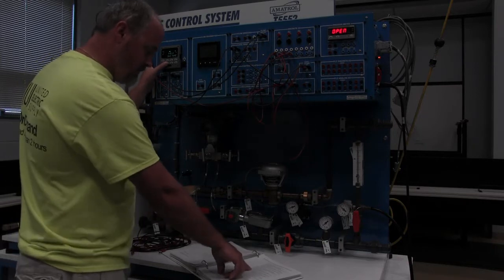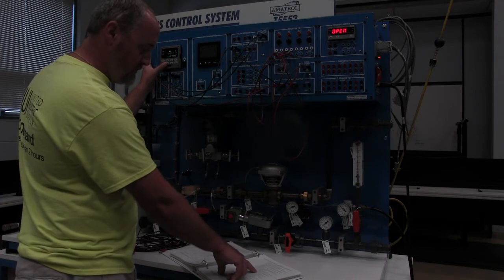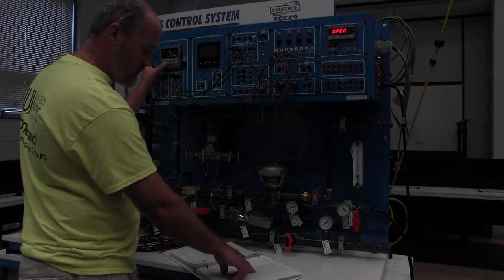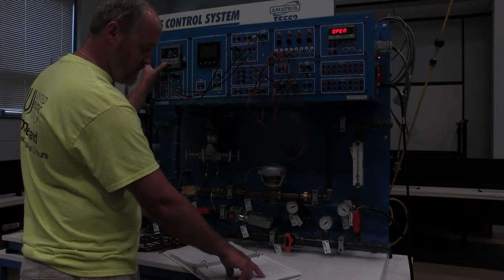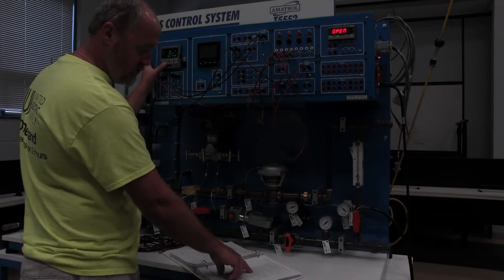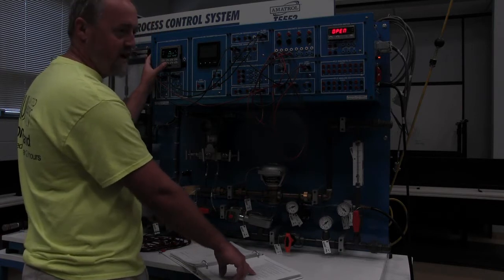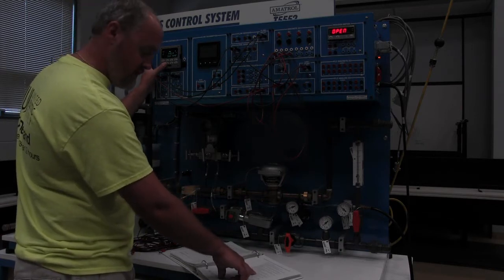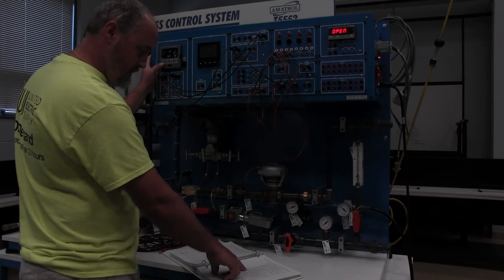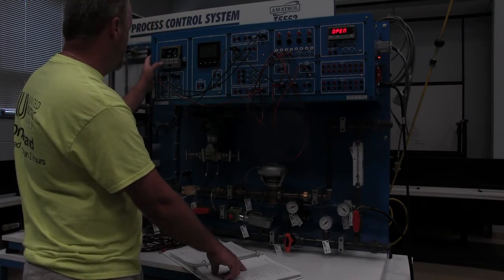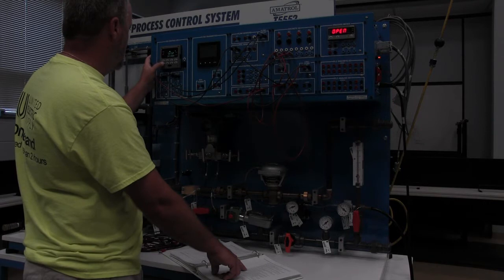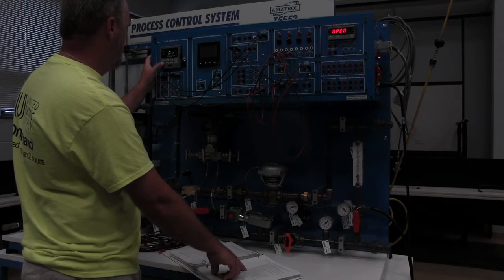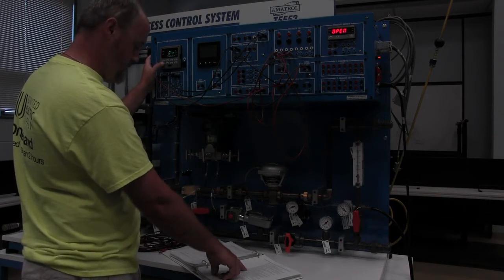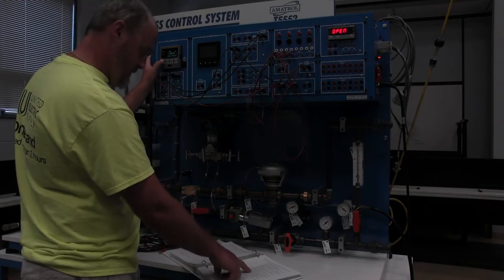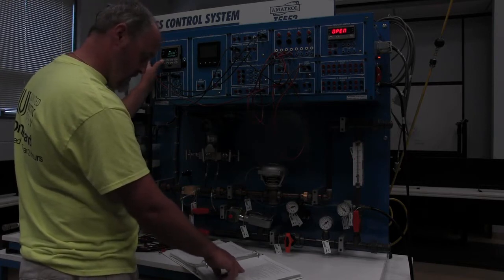The reason we're going 1 to 5 volts is the level sensor outputs a 4 to 20 milliamp signal. However, the input terminals of the loop controller have a 250 ohm resistor installed across them, which changes 4 to 20 milliamps to 1 to 5 volts. You'll see that a lot throughout the industry if you're using 4 to 20. Now we're going to press the function loop key. We got to get back to where we were first. Input 1. Now we're going to go to X-mitter. We want to be linear, which we are.